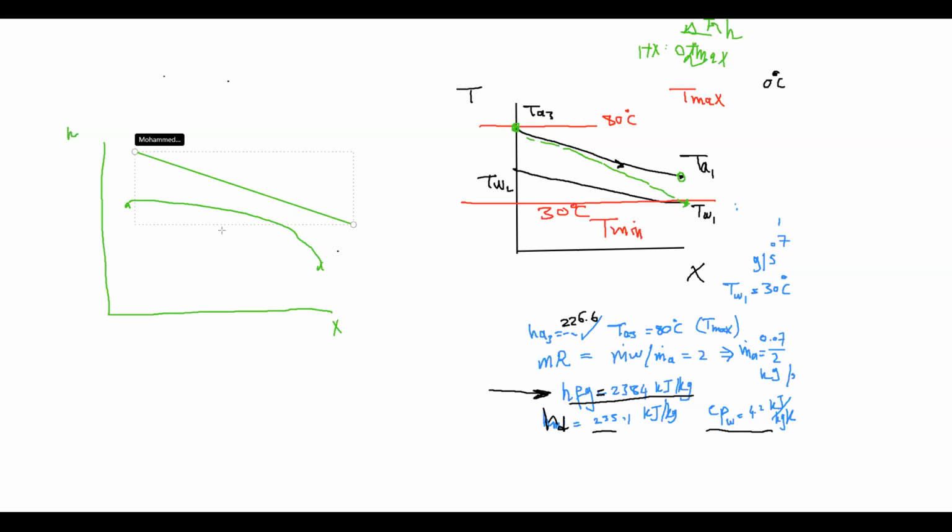In the humidifier, the difference at the terminal does not represent the minimum enthalpy difference. The minimum enthalpy difference is located somewhere in the middle, and that is what we call the enthalpy pinch. That becomes a little bit of a challenge, because you cannot just determine it by looking at the figure like we did for the dehumidifier.